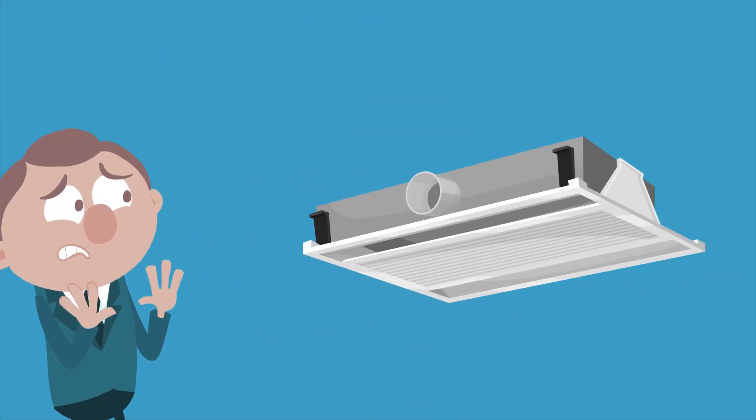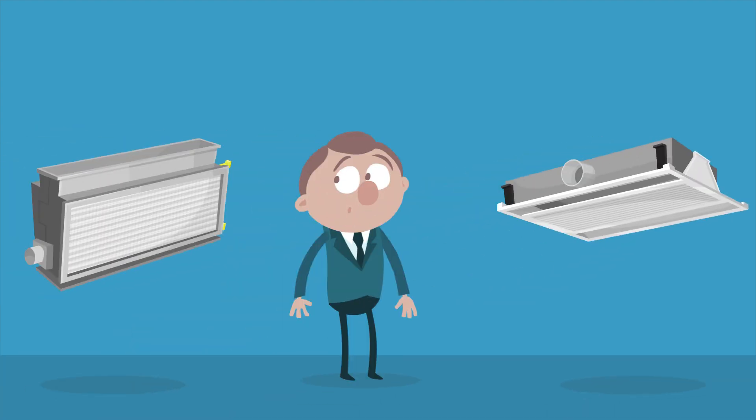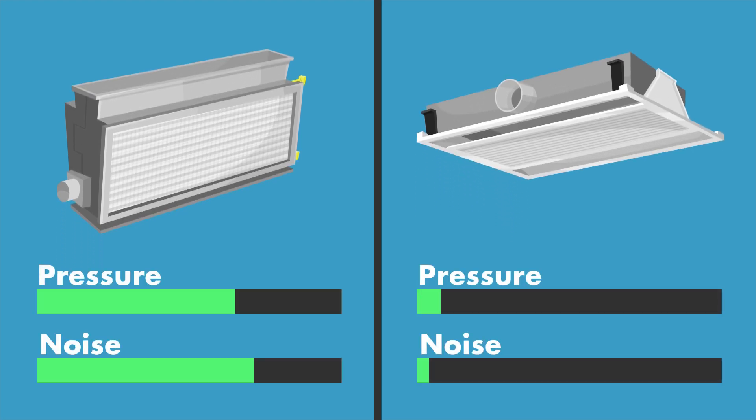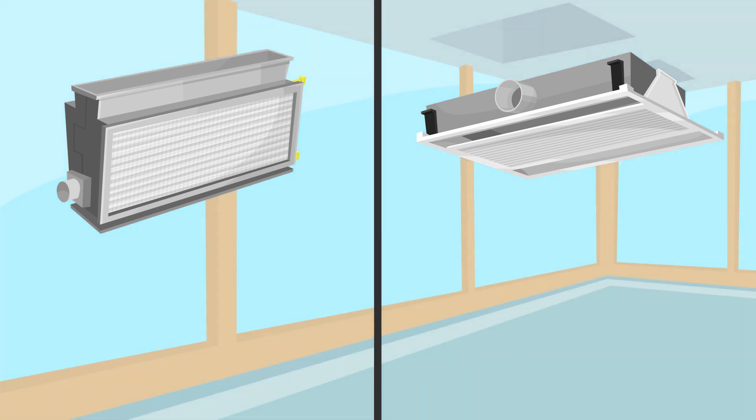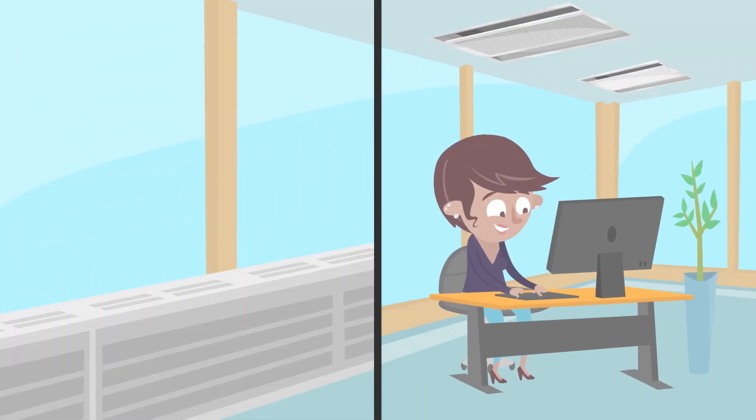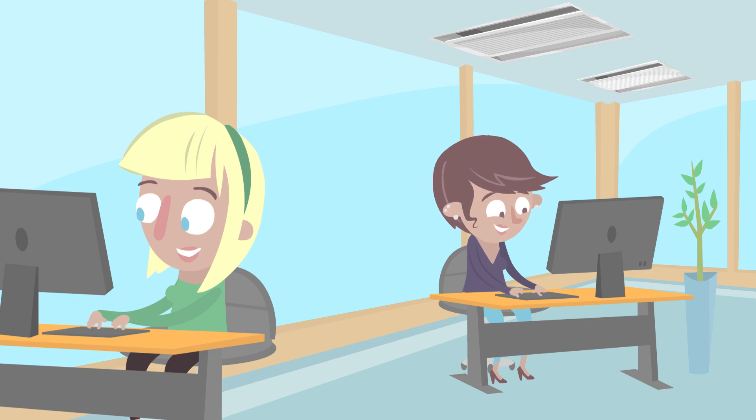At first, Albert was skeptical about active beams, until he realized that the technology is similar to perimeter induction units, which were commonly used until the mid-70s. Engineered to run at lower pressure and noise levels, and designed to fit into the ceiling, active chilled beams have all of the reliability and none of the drawbacks of the old PIU systems.